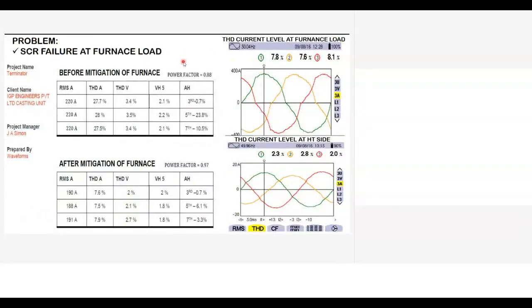Another thing, for the furnace load, is an arc furnace. With these arc furnaces, the current, the voltage, everything can vary a lot, especially when melting metals, the current can vary a lot. So this was the thing which we installed, and there were 220 amps.